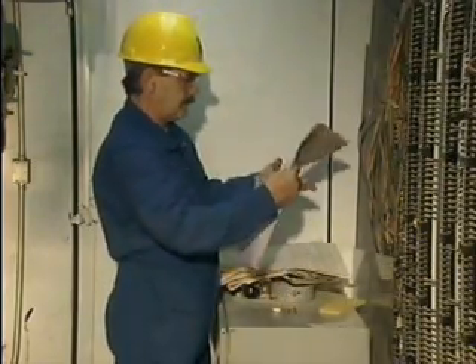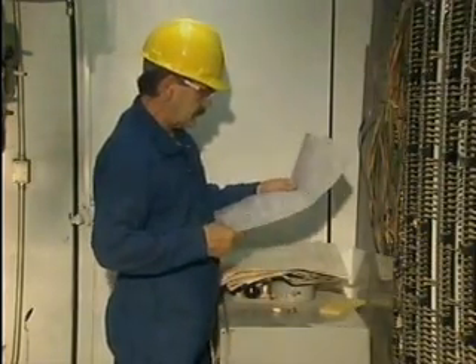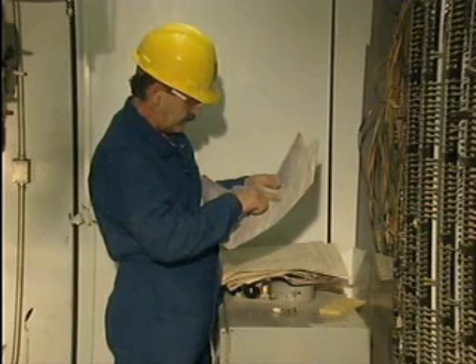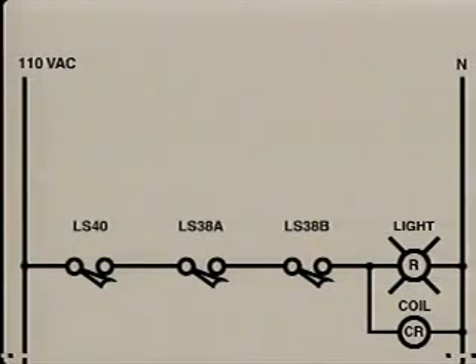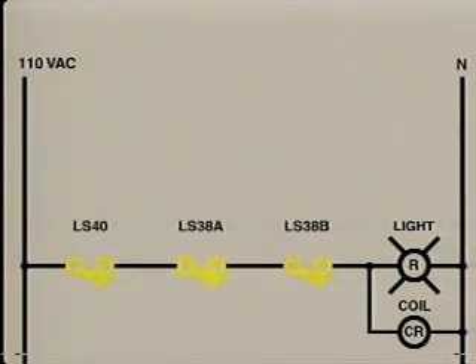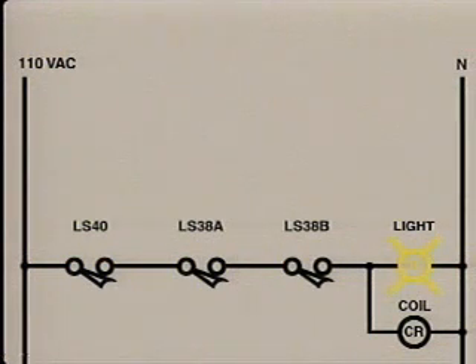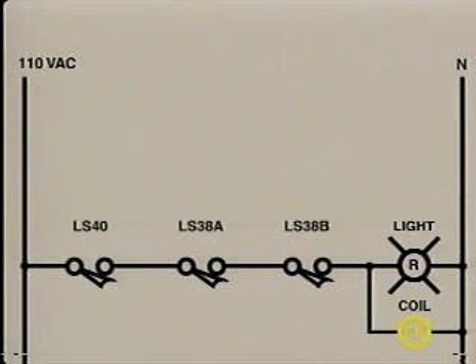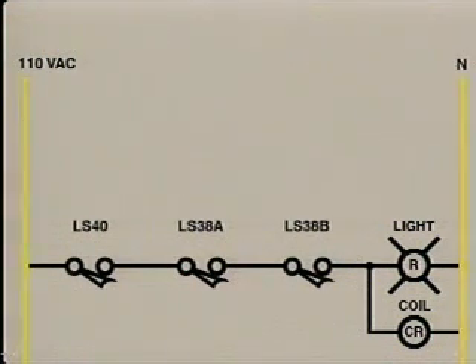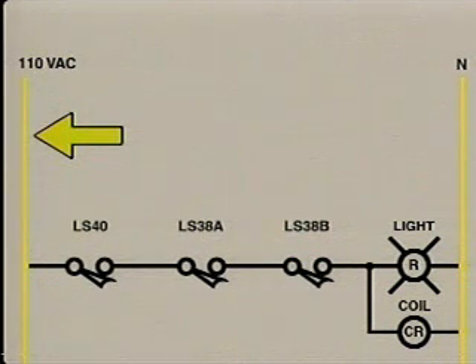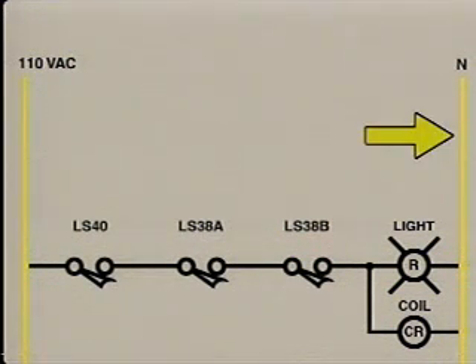Now the electrician can focus on the portion of the process that controls the operation of the B system silo crossover valve. This illustration represents the control circuit that he plans to focus on. This control circuit contains 3 limit switches, an indicator light, and a control relay's coil. The circuit's operating voltage is available on these lines.